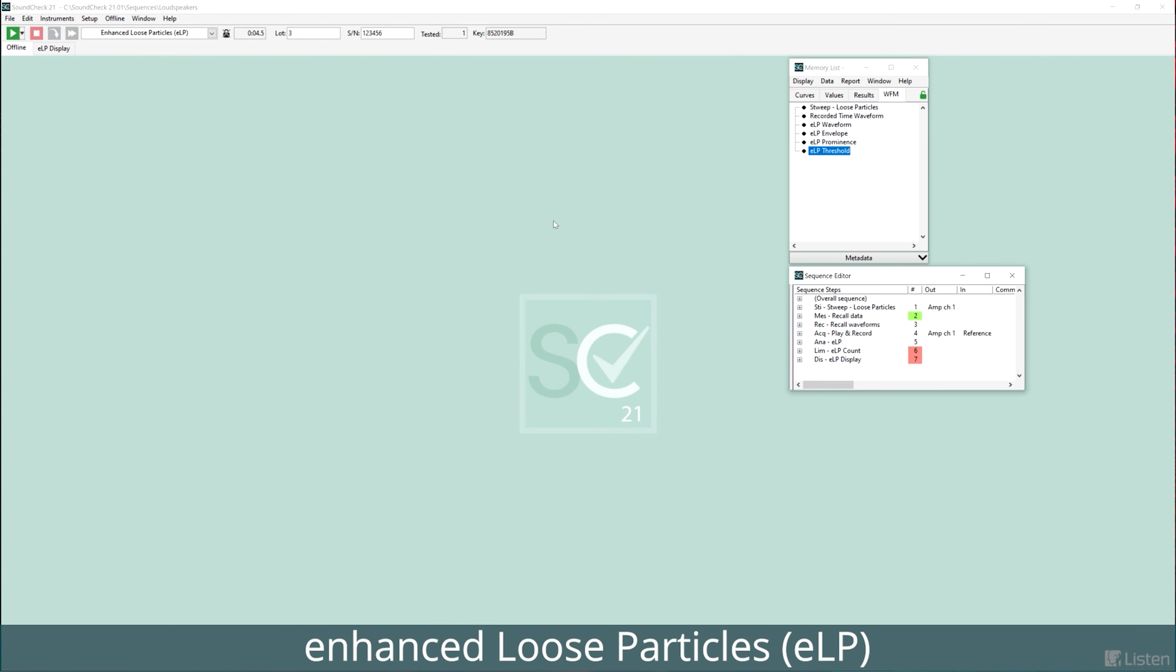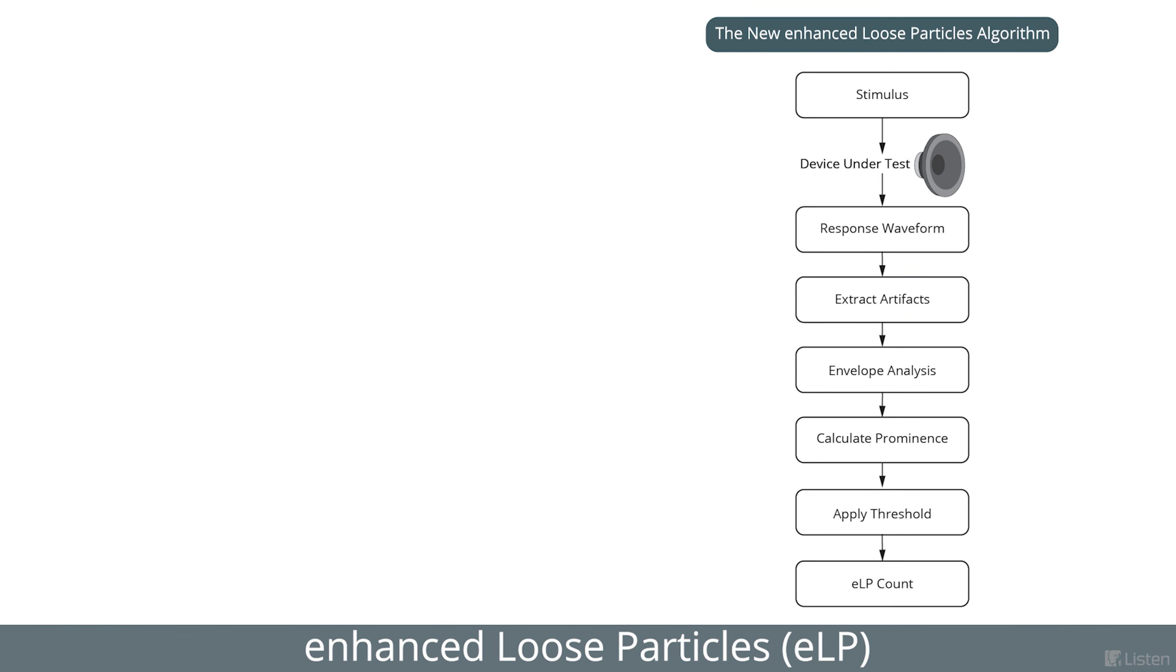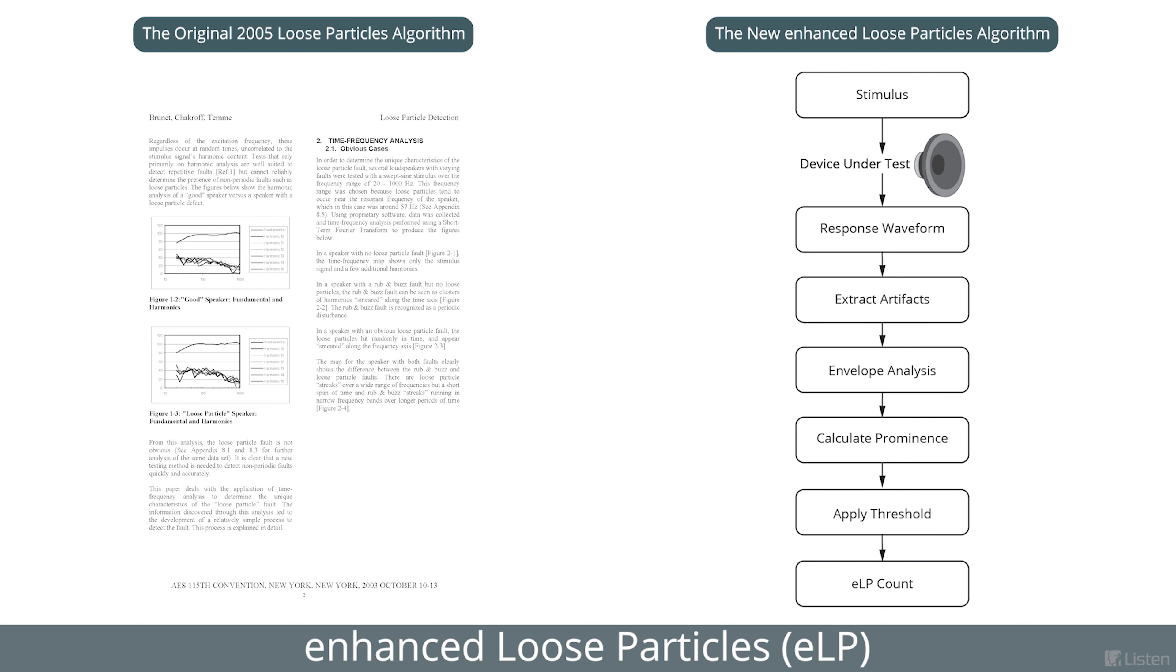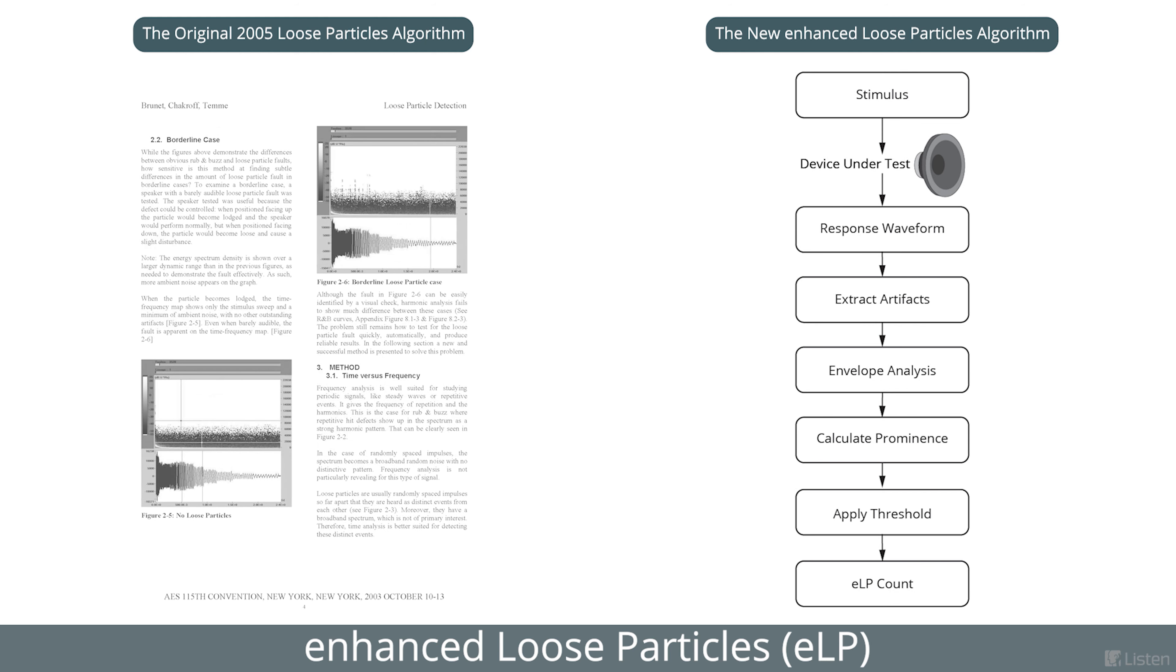Soundcheck's new Enhanced Loose Particle algorithm measures transient distortion independently of harmonic or rub and buzz distortion. This new algorithm builds on the success of our original 2005 algorithm and introduces advanced techniques to better highlight the loose particle defects while minimizing other artifacts. This makes it easy to set limits in line with subjective tests.